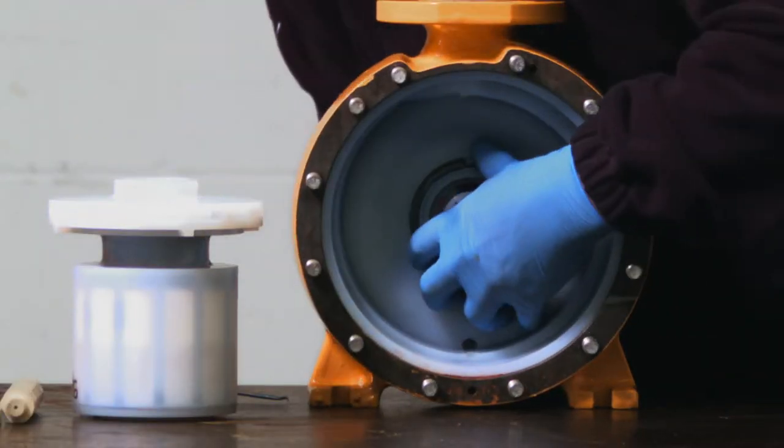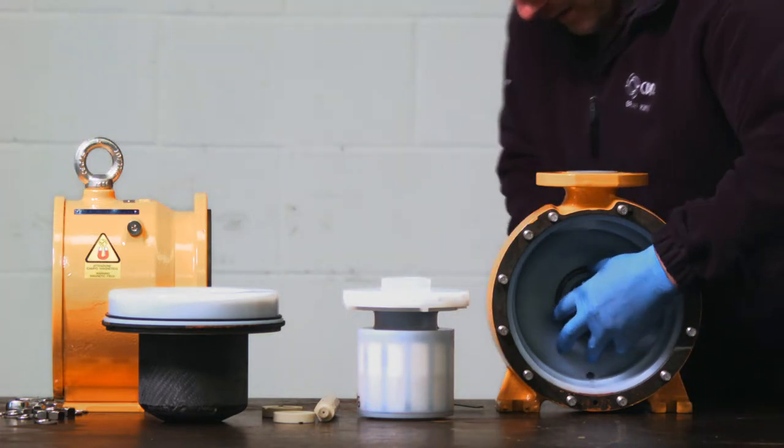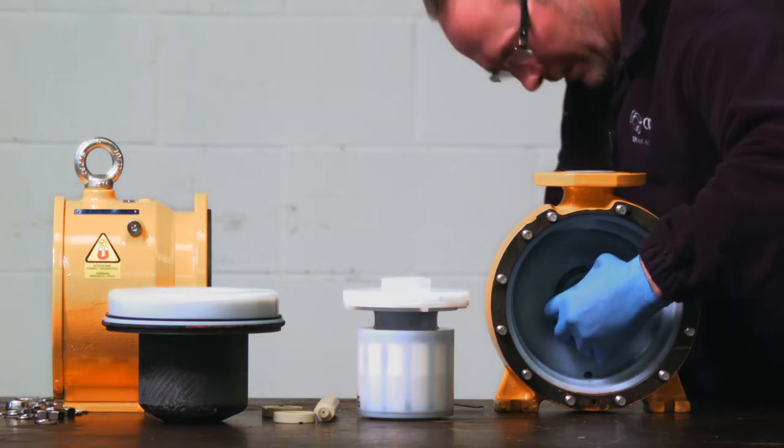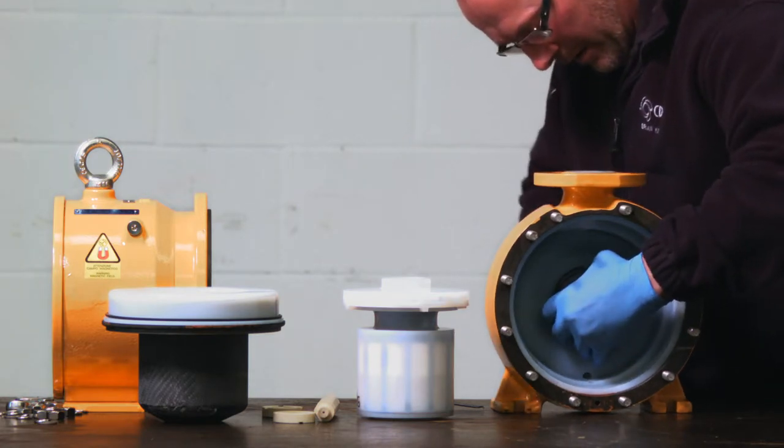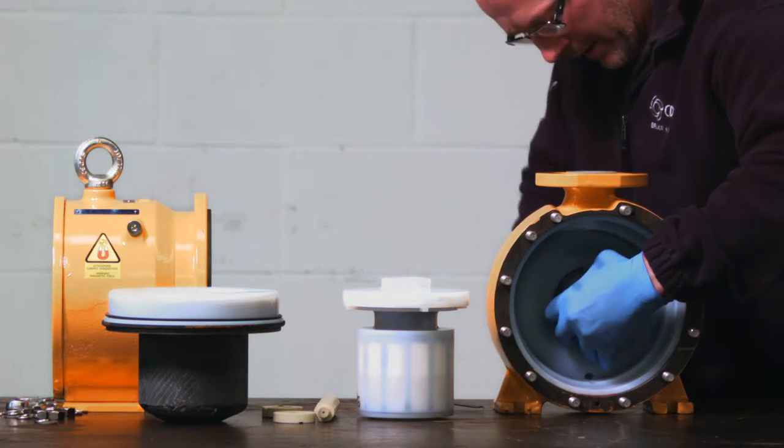The axial thrusts, like the smaller STN pumps, have grooves in them which need to face in towards the centre of the impeller assembly. These grooves assist with the flow of liquids for lubrication and cooling.